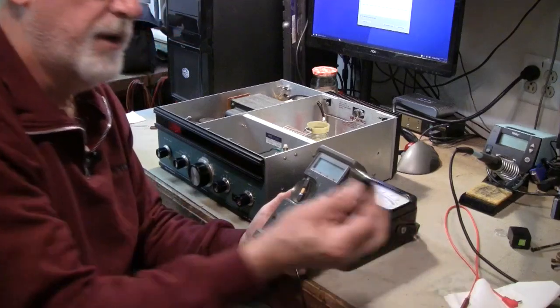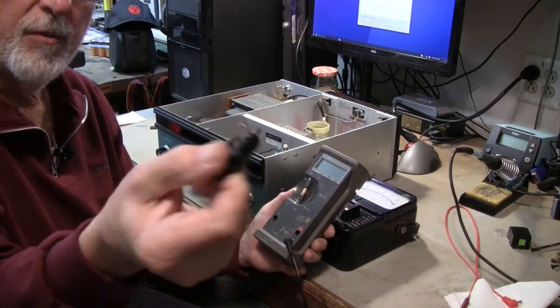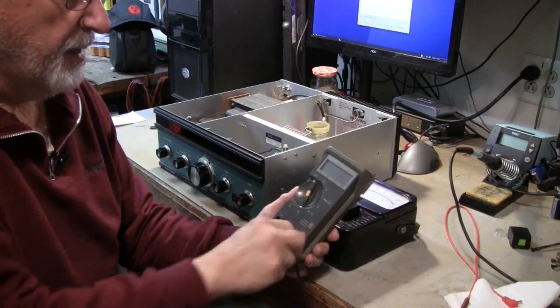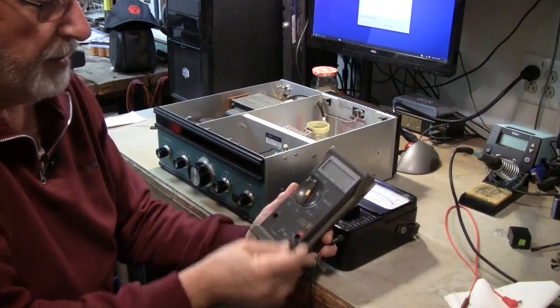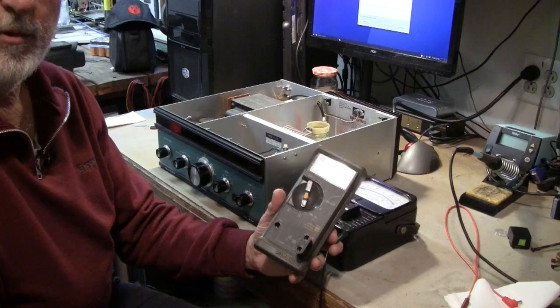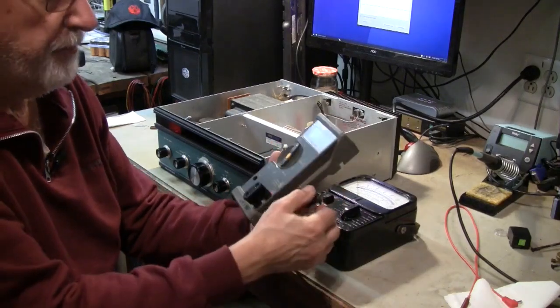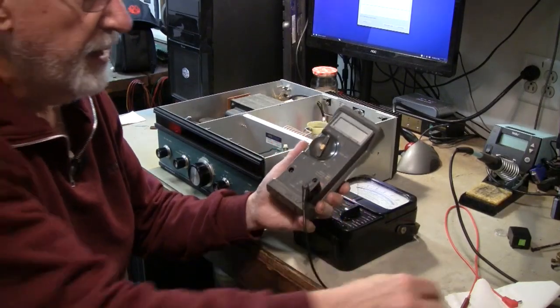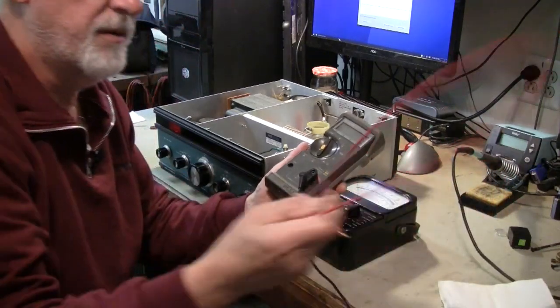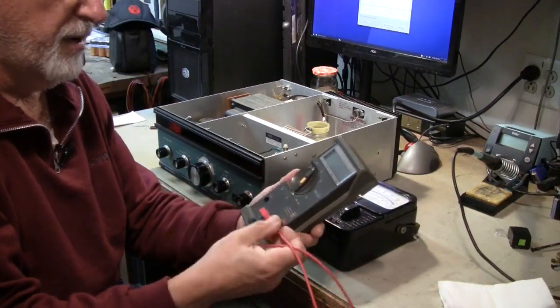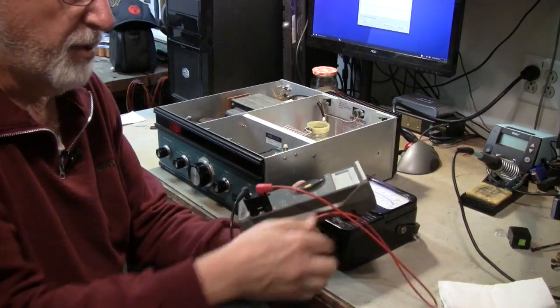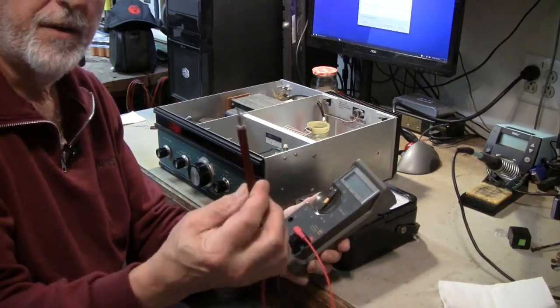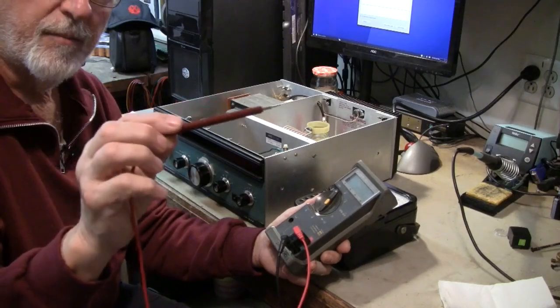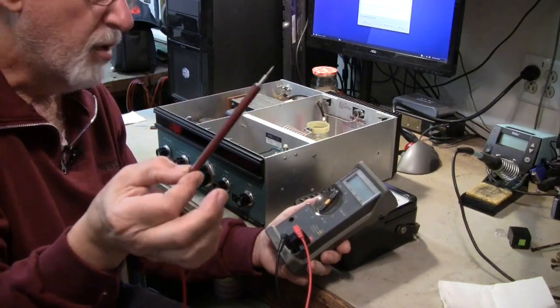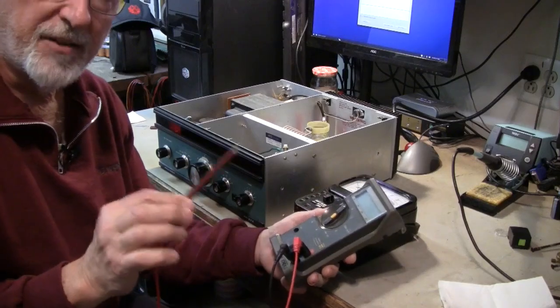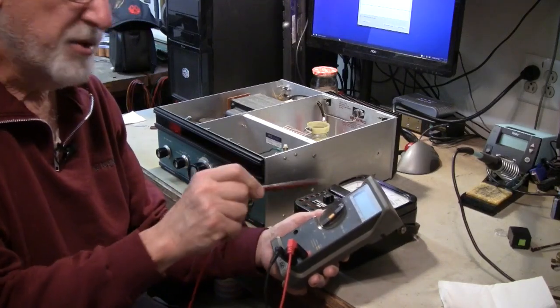I've got a banana plug jumper right here with a 1 mega ohm resistor on it that I add to the input terminals of the digital multimeter. Plug my negative here, and then I have a times 10 probe, a high voltage probe, that I'll plug into here with a 9.09 mega ohm calibrated precision resistor in the probe. That gives me a divide by 10 when I'm measuring voltage in the high voltage range.